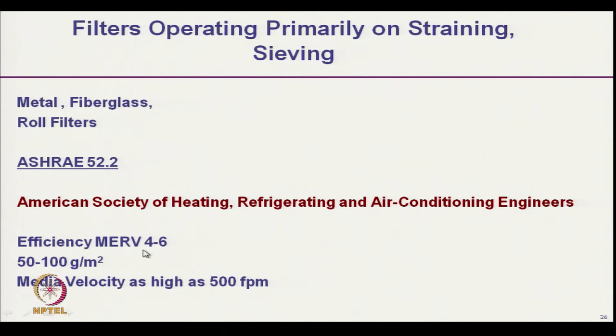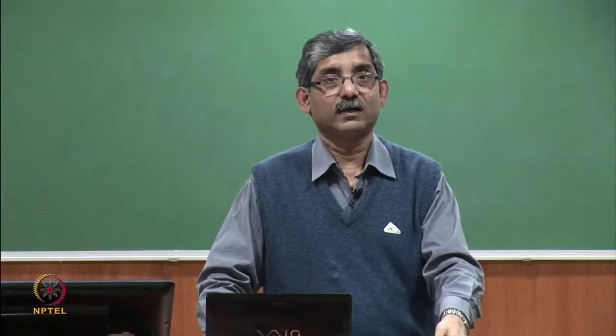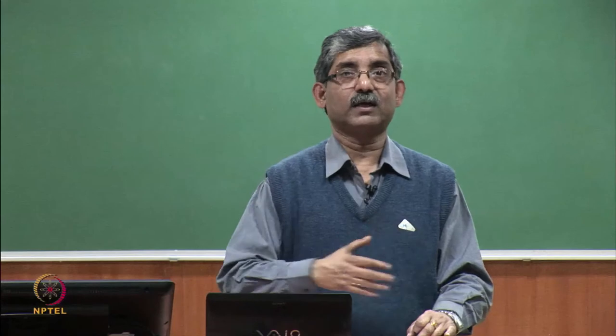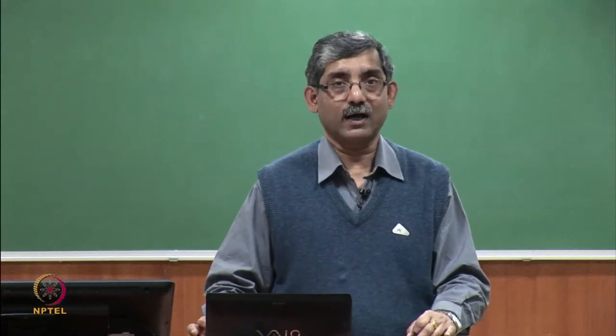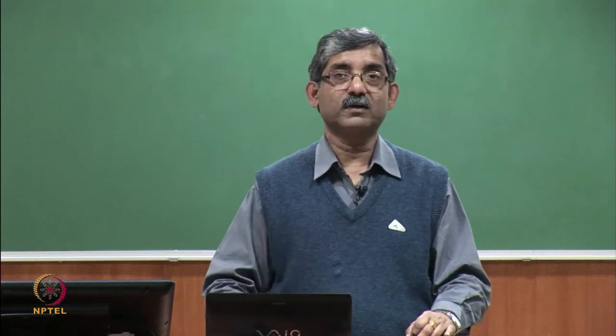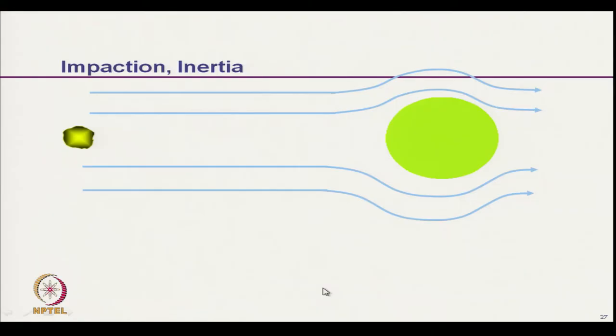A MERV value of 4 to 6 means lower filtration efficiency. This requires fabric with lower GSM — 50 to 100 grams per square meter. This type of filtration can take place at very high velocity. For coarser filtration we can use higher velocity, but for very fine particle filtration we have to reduce the fluid velocity.